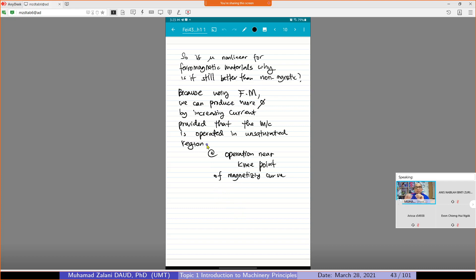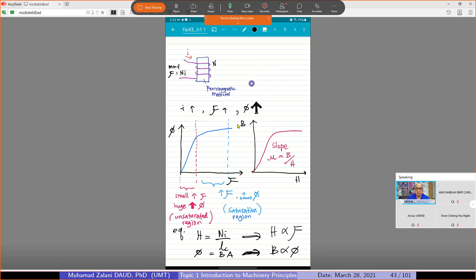Since ferromagnetic material will saturate after some time — after it is beyond the knee point — in electric machines, we will make sure that we operate the machine near the knee point. At a certain amount of current, if we add more current beyond that, the machine no longer functions efficiently, there will be losses. So we operate our machine near the knee point to ensure optimal operation.